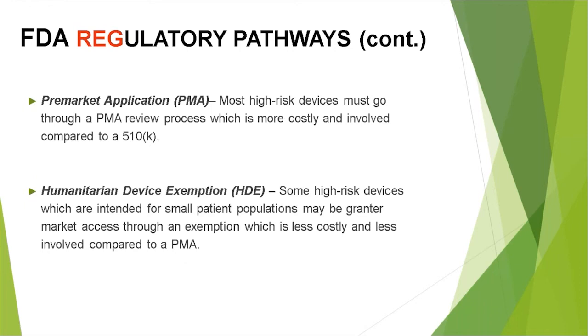Pre-market approval is the only real review and approval process of FDA. It's very rare. There's only a small number of devices which go through this pathway. It's very long, very expensive, but FDA does stand behind the safety and efficacy that can help sometimes manufacturers with post-marketing activities.